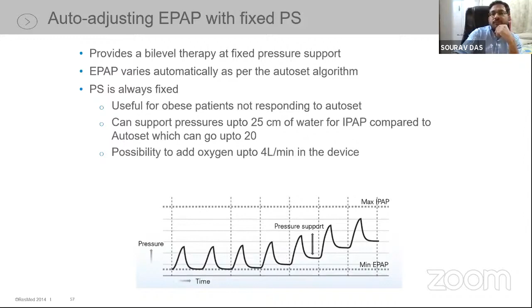So auto BiPAP is of course a very good option, but another comparatively cheaper option is auto-adjusting EPAP, that is expiratory positive airway pressure, with fixed pressure support. Pressure support means the difference between the inspiratory pressure and the expiratory pressure. So suppose the person needs 12 centimeters of water pressure during inspiration. It will have a fixed pressure support, let us say 6. And now when the person is breathing out, the person will breathe out against a pressure of 12 minus 6, that is 6 centimeters of water. So a higher pressure is given when the person is breathing in, and when the person is breathing out the pressure is much decreased, so it is much easier for the person to breathe out against that airflow. This is a very important tool which is often used in patients who have very severe OSA.